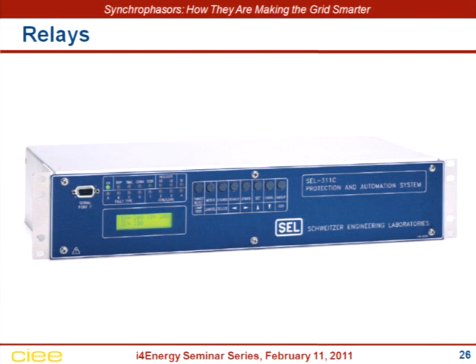But the relay used to work on a time over current electromechanical principle. Now, they're just little computers. This is a little rack mount, or could be a rack mount relay from Schweitzer Engineering Laboratories. They were one of the first to do digital relays. And the capabilities of this are immense, way more than most protection systems will ever use. But the system is very cost effective, very reliable.